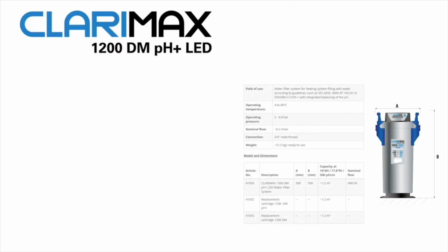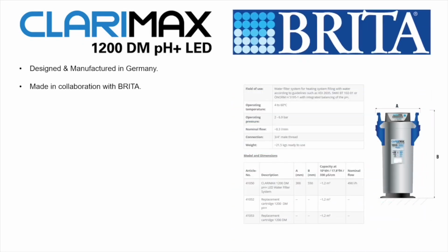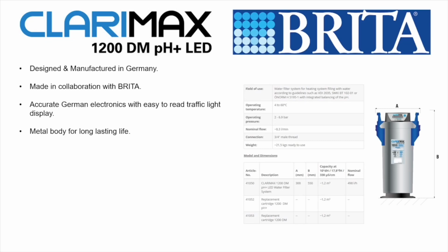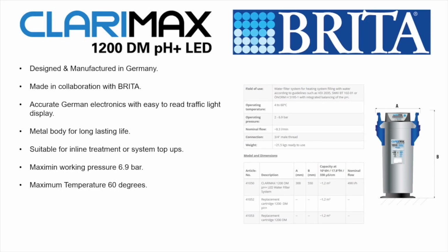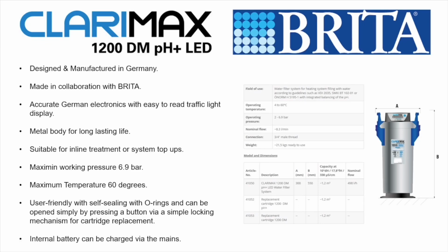The information on the Clarimax here: it was designed and manufactured in Germany, made in collaboration with Brita. Accurate German electrics with an easy to read traffic light display, metal body for long lasting life. It is suitable for inline treatment or system top-ups. Maximum working pressure just under 7 bar, maximum temperature 60 degrees. It's user-friendly with self-sealing O-rings and can be opened by pressing a simple button, and it's a really simple twist mechanism we're using. A really good bit about Clarimax is the water doesn't actually go inside it. Everything is withheld within the cartridge itself.